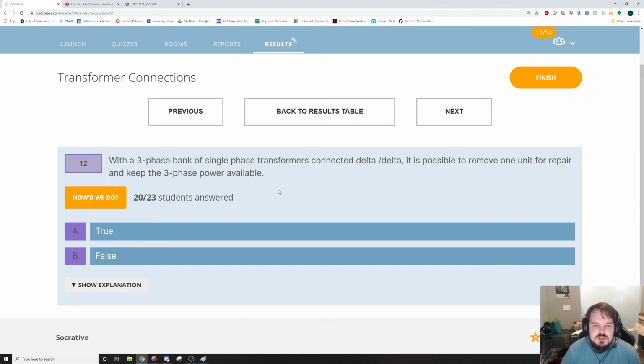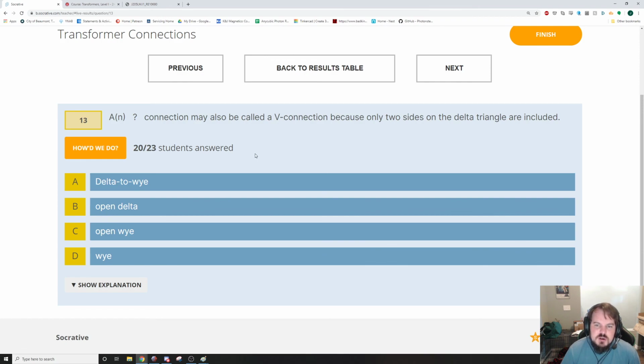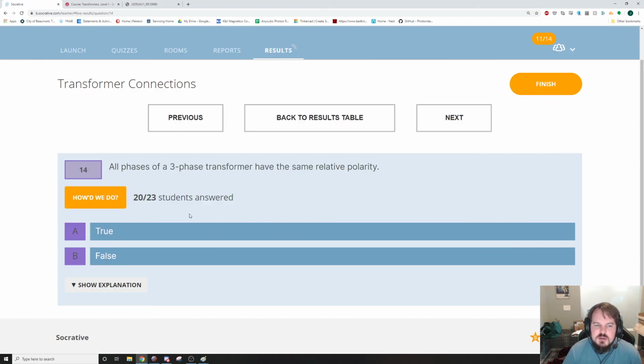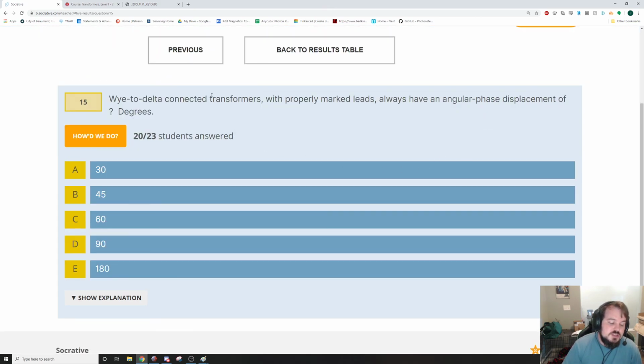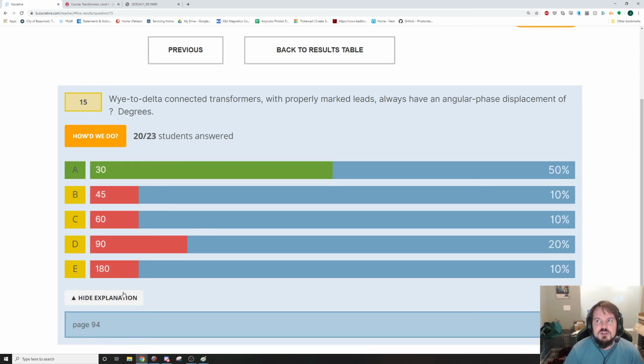A three-phase bank of single-phase transformers connected delta delta. Yeah. A blank connection may also be called a V connection because only two sides of the delta triangle are included. Open delta. So we have 3 or 4 questions about open deltas. So yes, all 3 phases will have the same relative polarity to each other. And you can see all those relative polarities in, I think, about page 93, 94. Actually, this one is on page 94. So around there in your book, you'll see a lot of those.